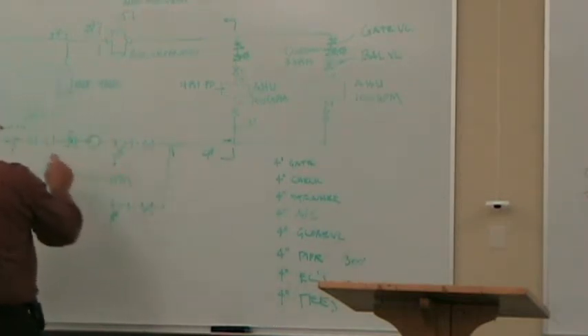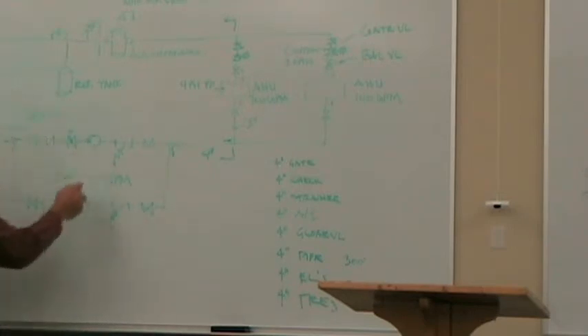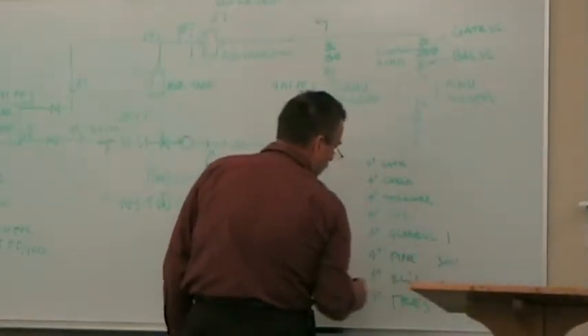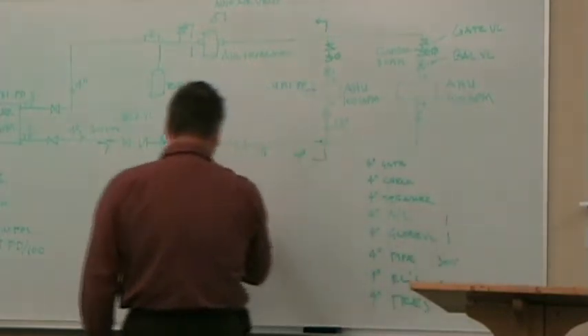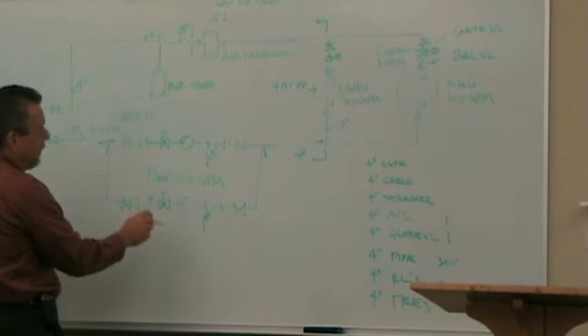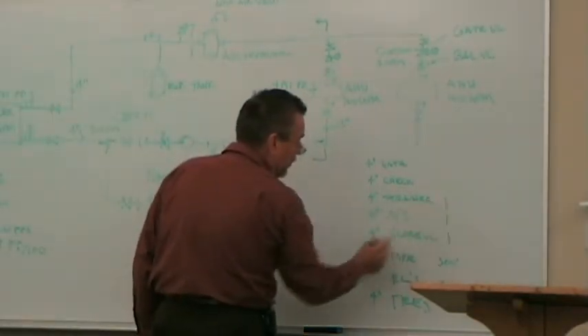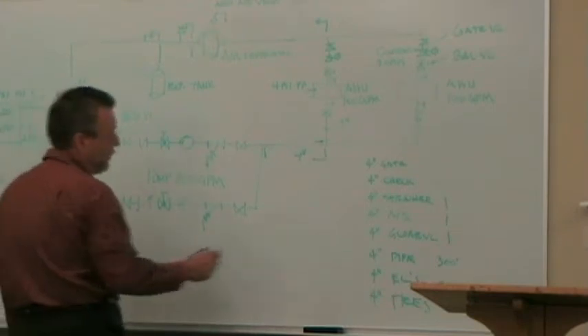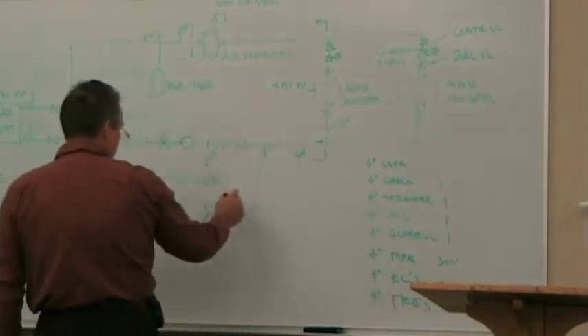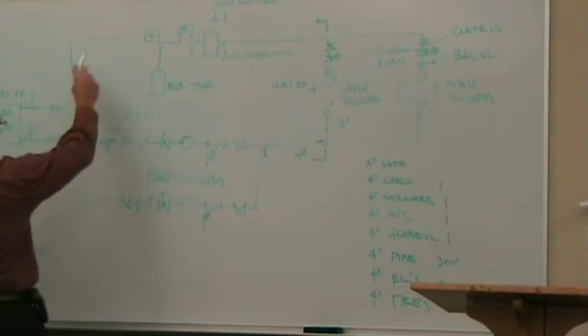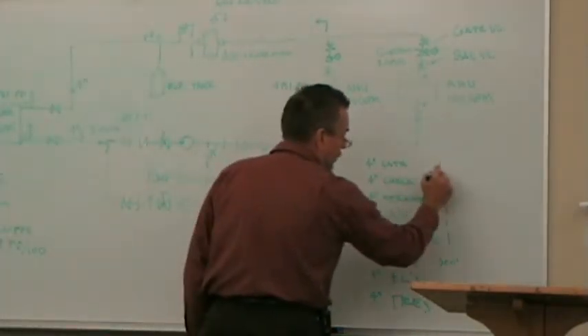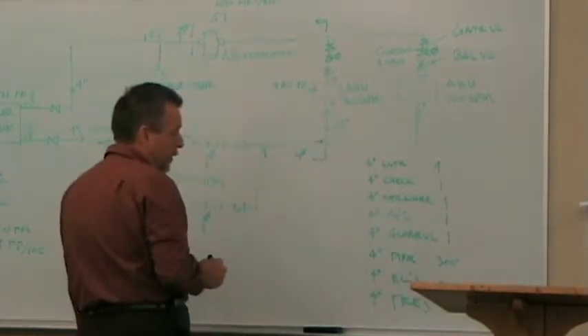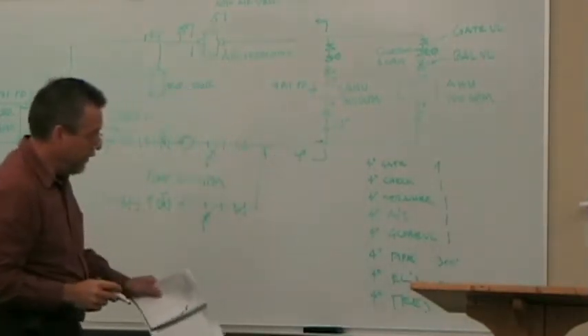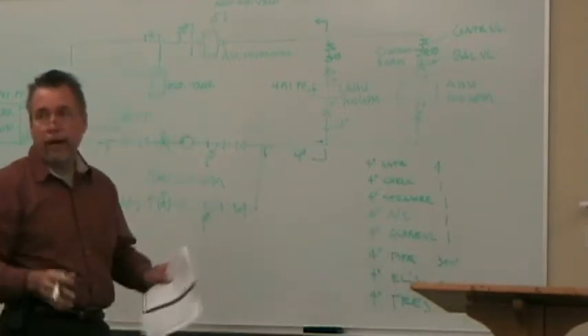And I've got globe valves. I've got balancing valves on each pump, but these pumps are in parallel, one's redundant, so I really only have flow through one pump. I'm only going to add up one balancing valve right there. Air separator, I've got one of those. One Y strainer here in front of the pump, to protect my piping system. Got one of those. Got one check valve on the pump. And I've got 1, 2, 3, 4 gate valves. Okay, so I add all these things up, and what it's going to do is give me the equivalent feet of pipe that I've got.